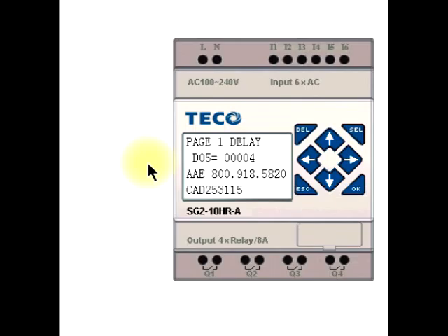It's currently set on 4 seconds. And what this does, if you just turn the control on and off, it will come up to the load material 1, load material 2 page, in this case for 4 seconds, which isn't long enough to do anything. I'm going to change that to 60 seconds. That's what I would recommend.